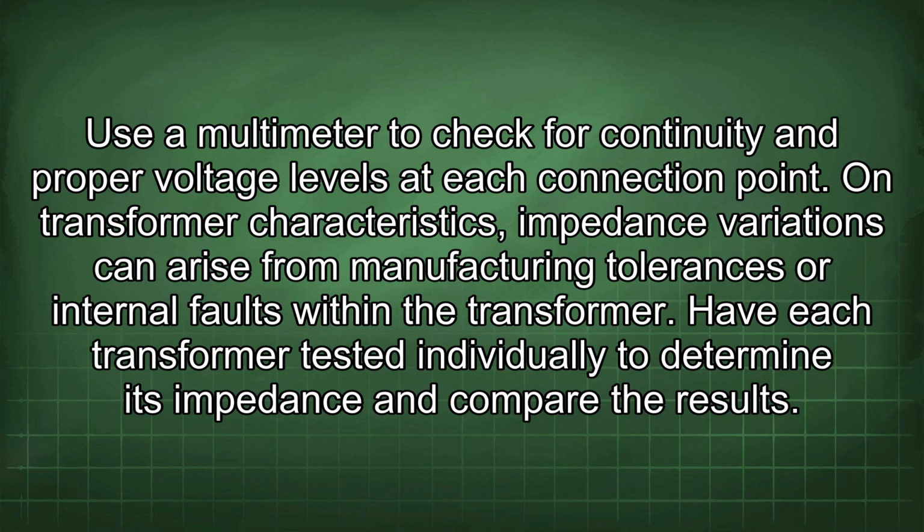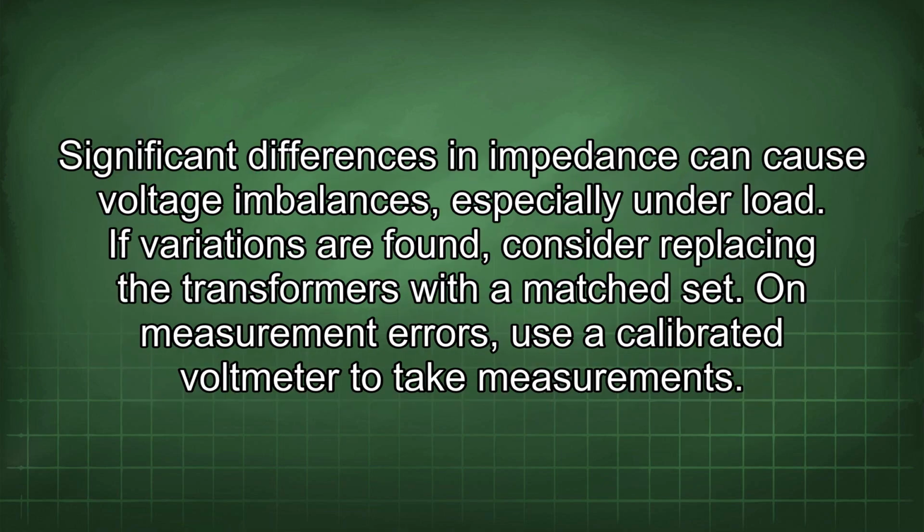On transformer characteristics, impedance variations can arise from manufacturing tolerances or internal faults within the transformer. Have each transformer tested individually to determine its impedance and compare the results. Significant differences in impedance can cause voltage imbalances, especially under load. If variations are found, consider replacing the transformers with a matched set.